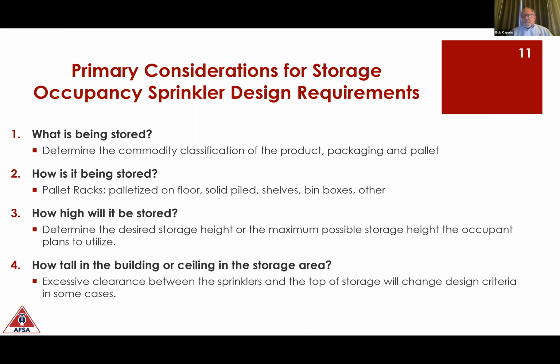So I'll put it this way. If I burn a block of wood that weighs 1 pound, the BTU, British thermal unit, measured from that 1 pound of wood is going to be around 8,000 BTUs. But if I take 1 pound of plastic, Group A plastic, polyurethane, polyethylene, polystyrene, and burn that same 1 pound, my BTU heat release rate is going to be just shy of about 20,000 BTUs. So really almost 3 times more heat.